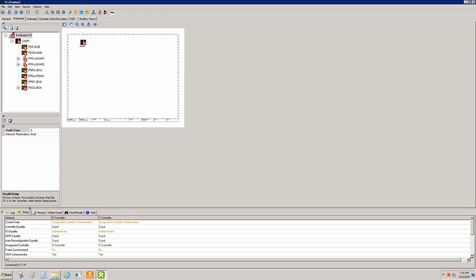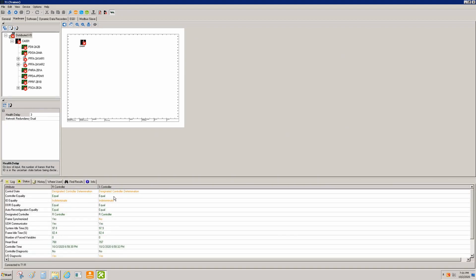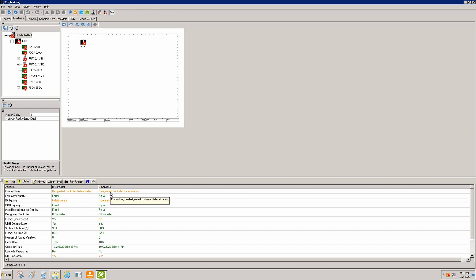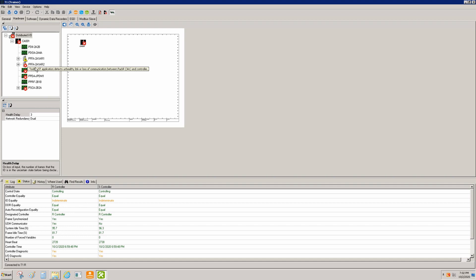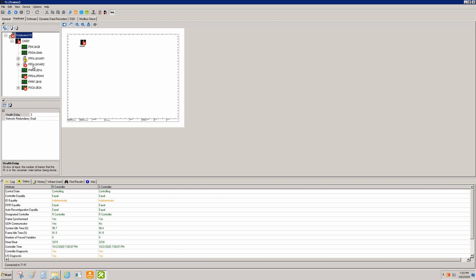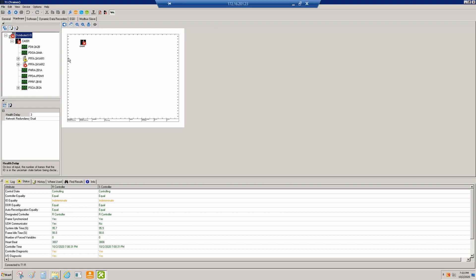If we check our status, we'll see the controller is going through its reboot — we just have to wait on that. Now we're waiting for the rest of the IO to come back up. Now that we have the controllers controlling and equal, we should see one by one these cards start reporting as they go through their boot-up process. We didn't really download to our PFFAs yet, so we're going to have to download again once most of the IO is back — with the exception of the PFFAs.